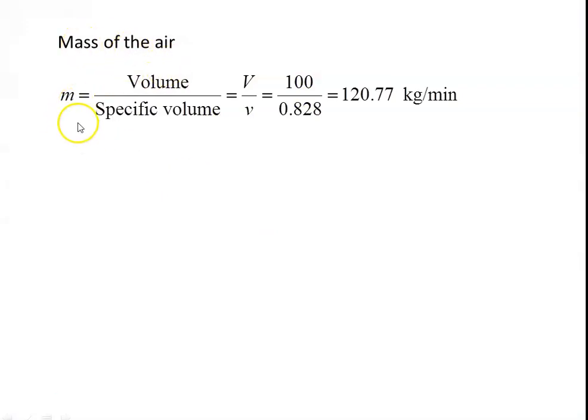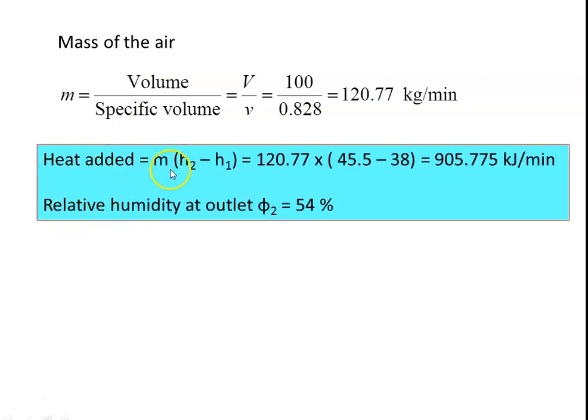Calculate the mass of the air: M = volume / specific volume = 100 / 0.828 = 120.77 kg/min. Heat added = M × (H2 − H1) = 120.77 × (45.5 − 38) = 905.775 kJ/min. The relative humidity at the outlet, directly from the psychrometric chart, is 54%. So heat added is 905.775 kJ/min and relative humidity at the outlet is 54%.